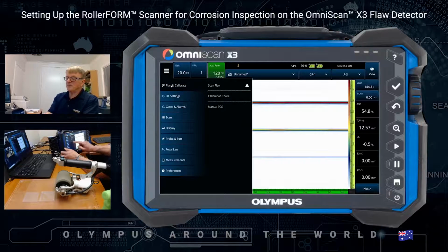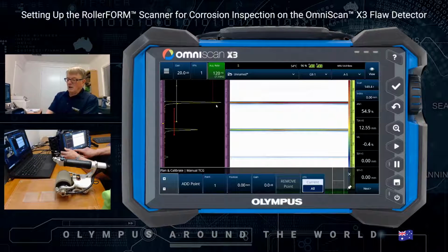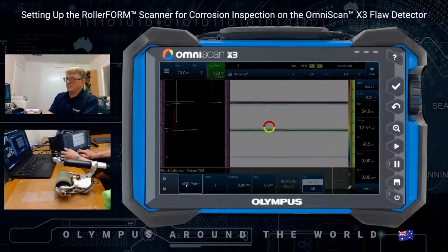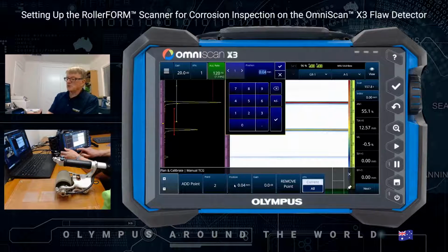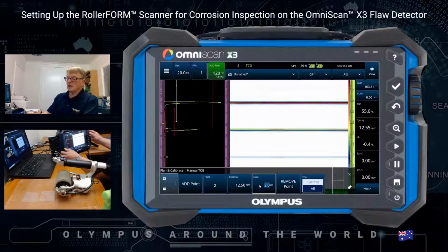So we'll do a TCG, a manual TCG, to compensate for that. So obviously the first point, there's no gain, we'll just add that. And then the second position, I'll make that the back wall echo, 12.5. And now we'll increase the gain slowly until it's the same as the interface echo. So that means that if there's any echo, any back wall if you like from corrosion, it will show the same size. That also means that if we can pick up a pit near the top and a pit near the bottom, they should both show the same size. Okay, so we've done that.